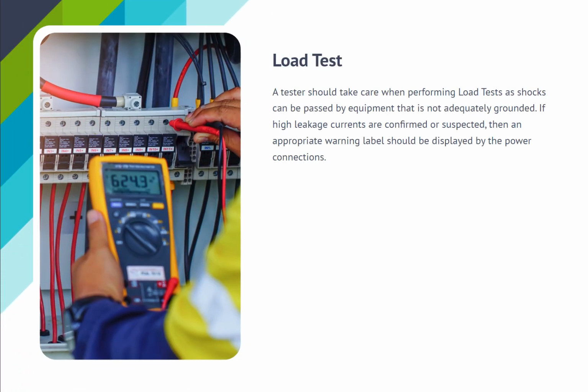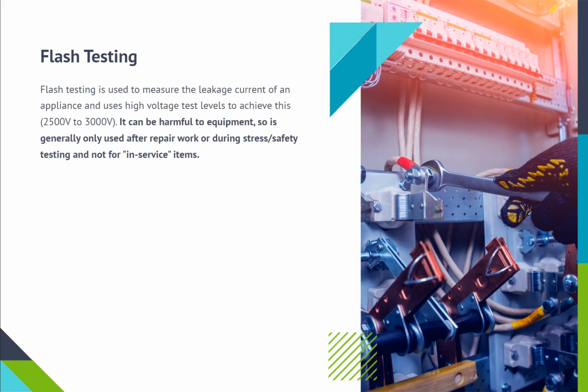A tester should take care when performing load tests, as shocks can be passed by equipment that is not adequately grounded. If high leakage currents are confirmed or suspected, then an appropriate warning label should be displayed by the power connections. Flash testing. Flash testing is used to measure the leakage current of an appliance and uses high voltage test levels to achieve this, 2500 volts to 3000 volts. It can be harmful to equipment, so is generally only used after repair work or during stress or safety testing, and not for in-service items.